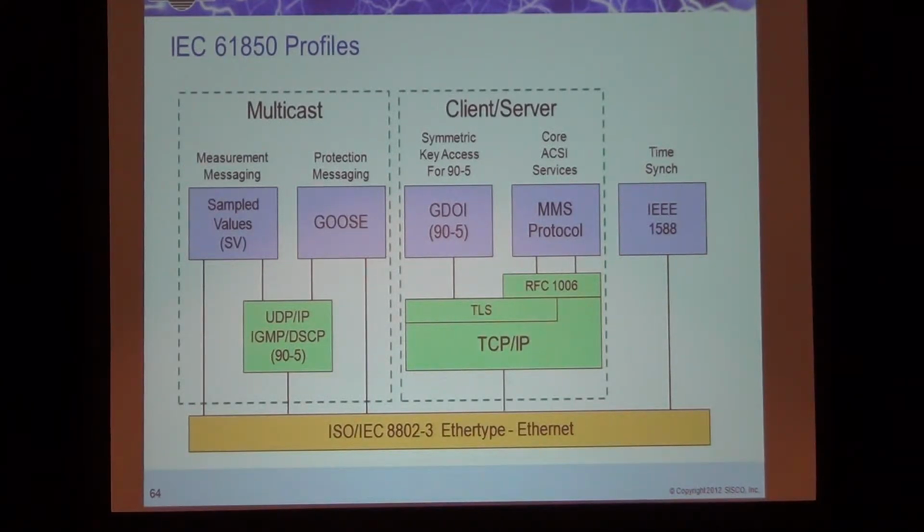We have the traditional profiles of sampled values and GOOSE that go directly to Ethernet. And that's been designed primarily for a single substation type of application, although there are systems that can distribute that over wide area networks.